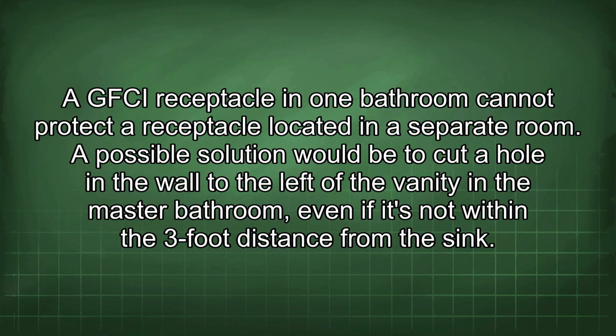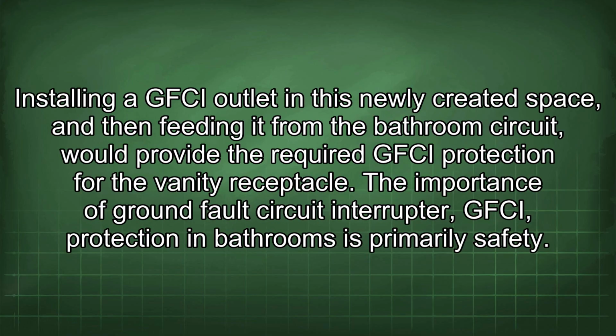A possible solution would be to cut a hole in the wall to the left of the vanity in the master bathroom, even if it's not within the 3-foot distance from the sink. Installing a GFCI outlet in this newly created space, and then feeding it from the bathroom circuit would provide the required GFCI protection for the vanity receptacle.